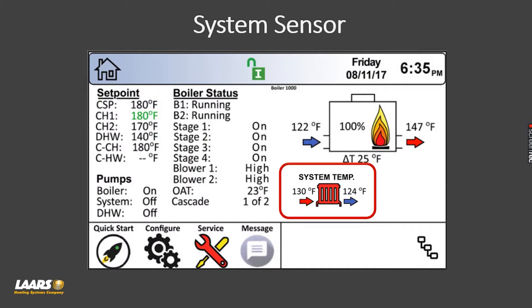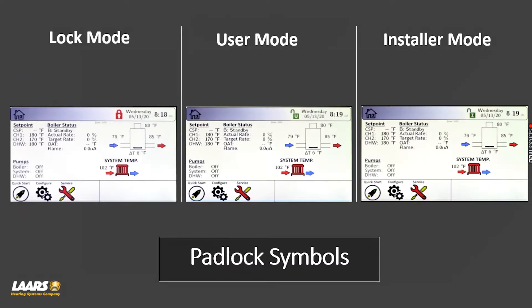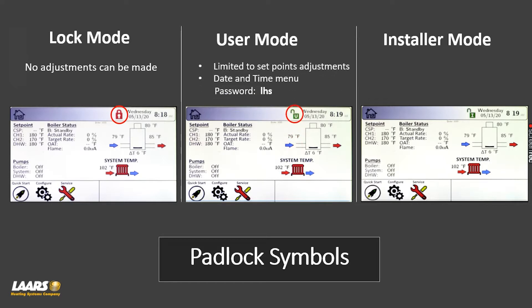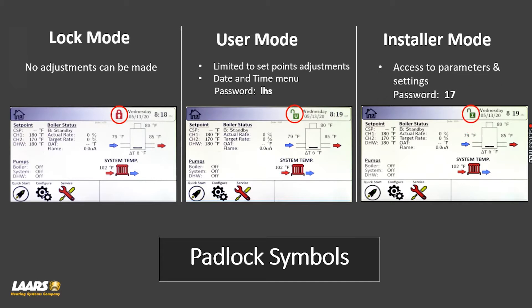On that lead boiler, on the home screen you should see the icon for the system sensor. We'll also talk about the padlock symbols — there are three padlock modes: lock mode where no adjustments can be made, user mode where you can only make setpoint adjustments, and installer mode. For cascading, you want to be in installer mode and that password is 17.